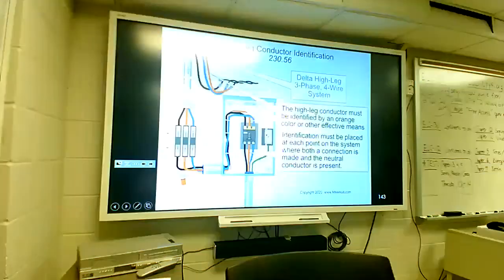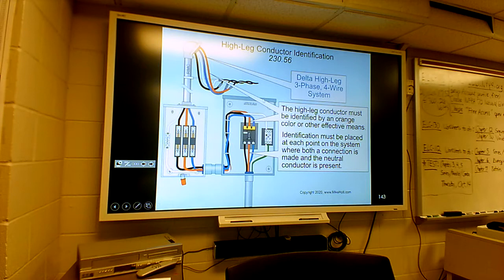High leg conductor identification. This is something that those of you that have commercial wiring have already heard about. If the transformer outside that feeds your building is a delta transformer with what they call a high leg, which is not common, but every now and then you may see one on older things. I don't know of anything on newer buildings that's done like this. If it's a delta transformer in the yard feeding your building and it has what they call a high leg, the high leg needs to be orange.